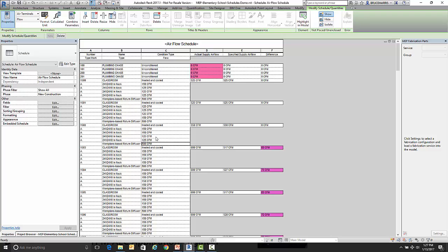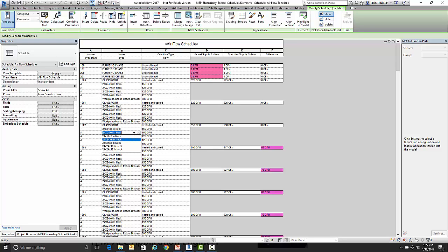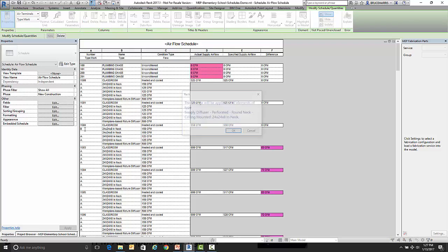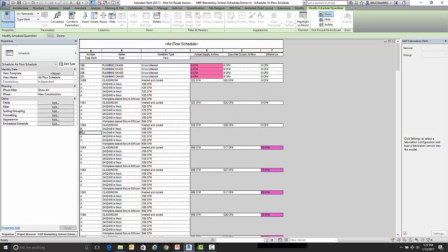Not only can I change the CFM, but if I needed to, if I went up to say I had to go up to 250 CFM in one of my spaces, I could go in here and I could also change the neck. So I'm going to go up to 8 inch neck on these two ones in this room that are 150. Now notice their type mark went away. So they're no longer a type A diffuser. Let's say I want that to be a type B diffuser is my 8 inch neck. So when I put that in there and say yes, then it populates all the 8 inch necks with a type B. So not only can I change the CFM within a schedule, but I can also change the actual neck size or the family member within a schedule as well.